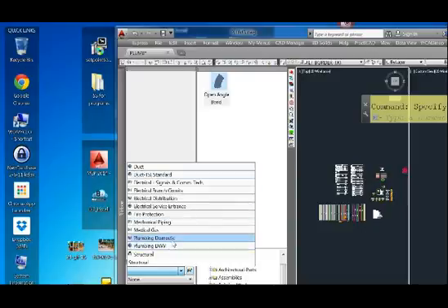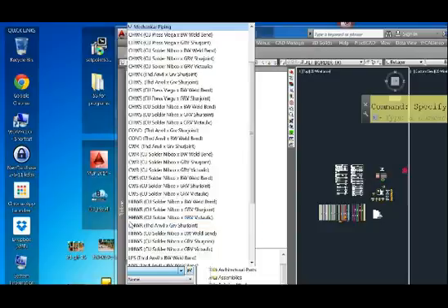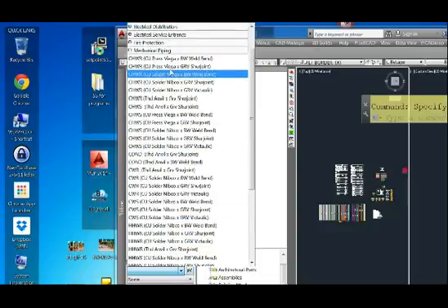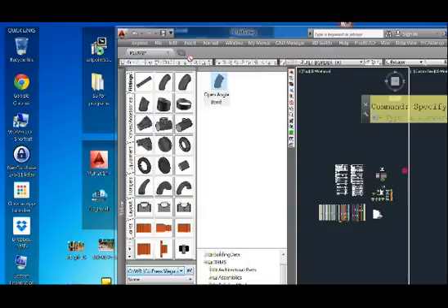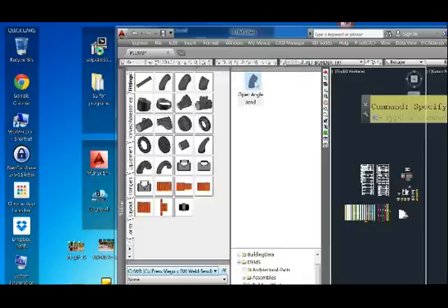So if you wanted to pick right now, I think this open angle bend is meant for welds. Right. If you want to make one for like PVC or something like that, you need to change its materials. Right. You need to copy it, paste it, and change its properties to match the service that you want to utilize it for. So if you did a design line right now with the welded system and you brought that open angle bend into it, right. There you go.